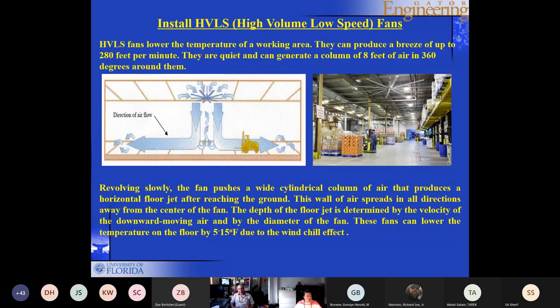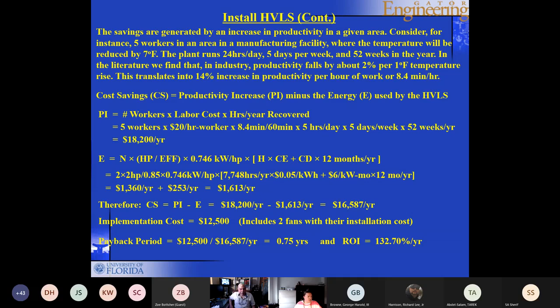The depth of the floor jet is determined by the velocity of the downward moving air and by the diameter of the fan. These fans can lower the temperature on the floor by up to 15 degrees Fahrenheit, anywhere from 5 to 15 degrees Fahrenheit, simply because of the so-called wind chill effect. So you haven't done any air conditioning here. You haven't spent any money on an air conditioning system, but just simply using these high volume, low speed fans, you can actually achieve a 5 to 15 degree reduction in temperature. Now, the question now becomes, how do we convert that into productivity savings? Or shall we say productivity improvement?